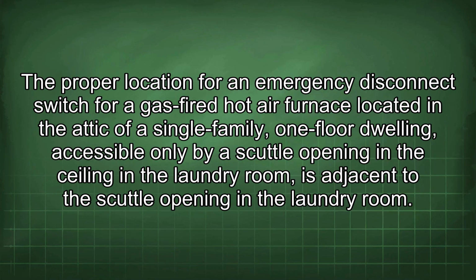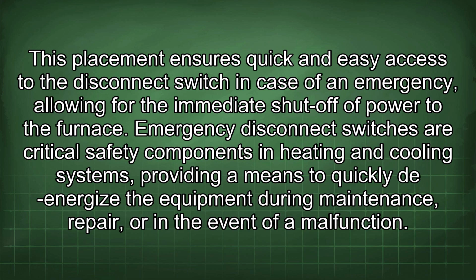The proper location for an emergency disconnect switch for a gas-fired hot air furnace located in the attic of a single-family, one-floor dwelling, accessible only by a scuttle opening in the ceiling in the laundry room, is adjacent to the scuttle opening in the laundry room. This placement ensures quick and easy access to the disconnect switch in case of an emergency, allowing for the immediate shut-off of power to the furnace.